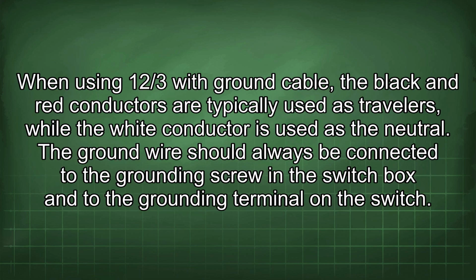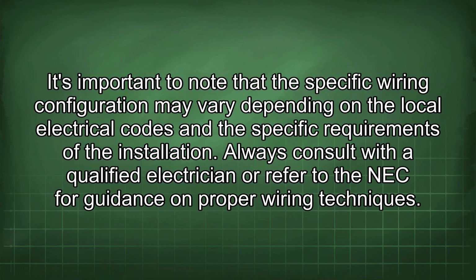When using 12/3 with ground cable, the black and red conductors are typically used as travelers, while the white conductor is used as the neutral. The ground wire should always be connected to the grounding screw in the switch box and to the grounding terminal on the switch. It's important to note that the specific wiring configuration may vary depending on the local electrical codes and the specific requirements of the installation. Always consult with a qualified electrician or refer to the NEC for guidance on proper wiring techniques.